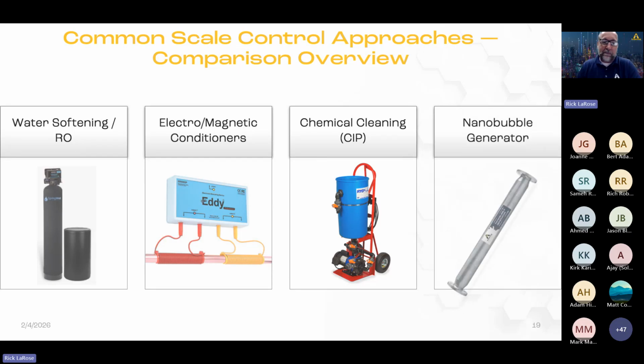So we're going to transition now and talk about nanobubbles, which is what you all came to hear about. Nanobubble conditioning is a non-chemical approach, but it works differently than the others. Rather than removing hardness and aggressively stripping scale, nanobubbles continuously condition the system. Keep in mind this is a conditioning process. What makes them distinct is that, done right, they gently remove existing scale over time, and at the same time—this is where the power is—they inhibit new scale from forming.